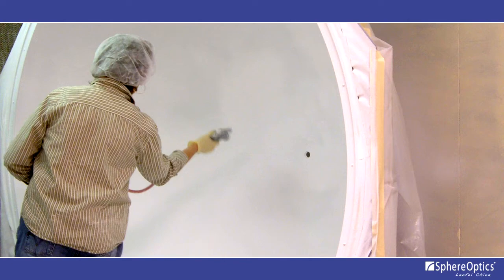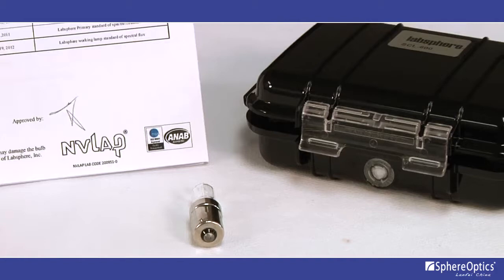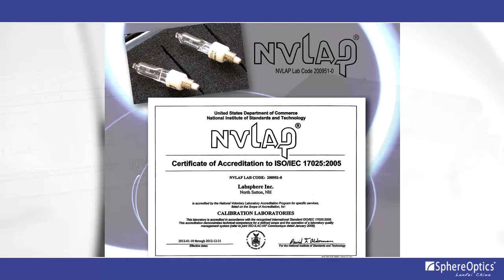Also included with each system is a NIST/NVLAP traceable calibrated lamp standard to ensure high accuracy and reliability. This allows users to perform simple in-house system recalibration and verification. These lamp standards are also supplied by LabSphere and are accredited under ISO IEC-17025.